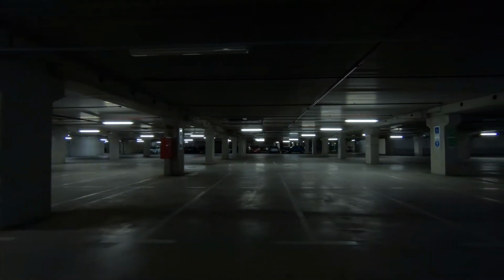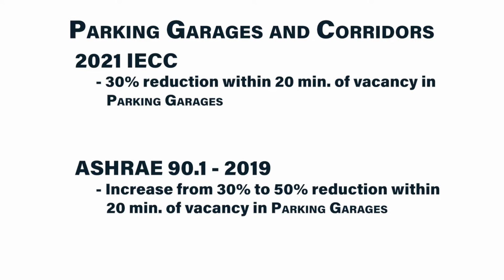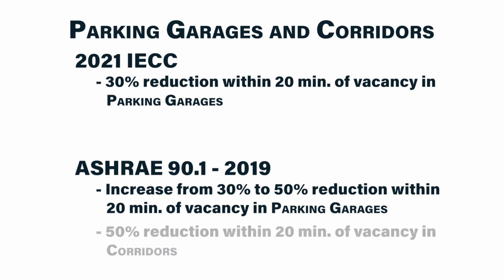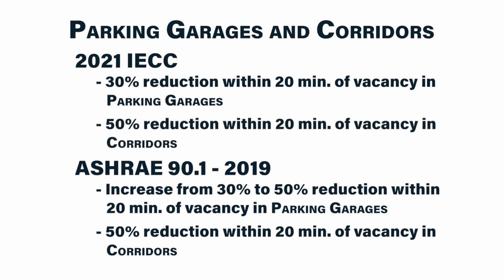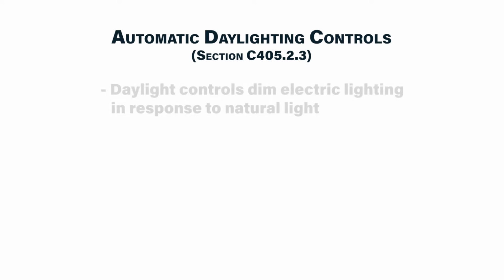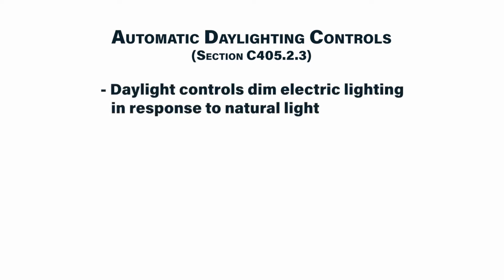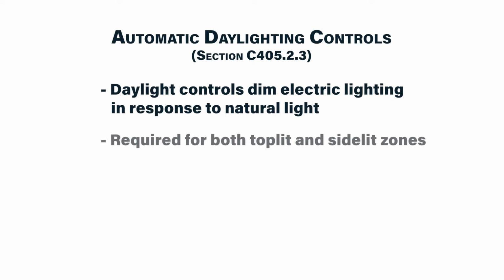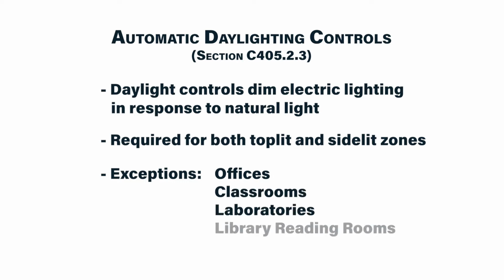feedback from occupants. Similarly, in corridors, ASHRAE 90.1 has been requiring the reduction of lighting by 50% within 20 minutes of vacancy since 2013, and IECC 2021 will add this control requirement. Current codes now require automatic daylighting controls that dim electric lighting in response to natural daylight in both side-lit and top-lit daylighting zones. These controls must dim lights to off in all but offices, classrooms, laboratories, and library reading rooms.